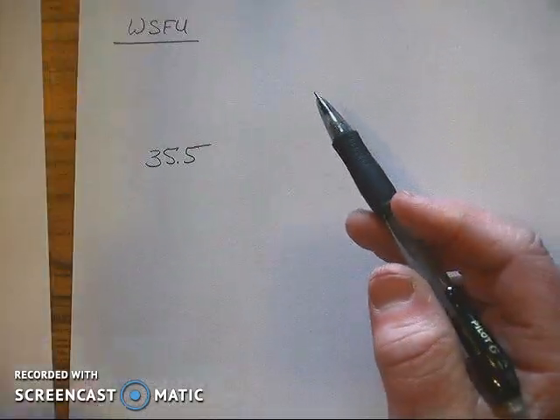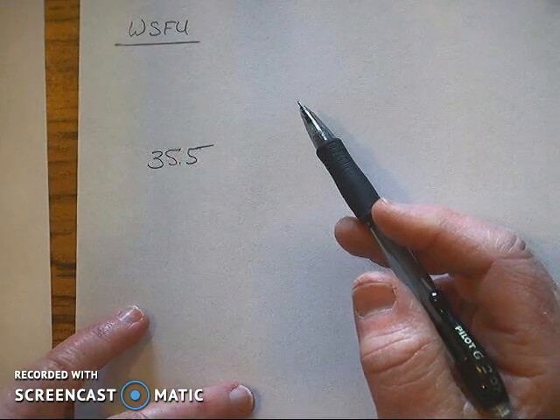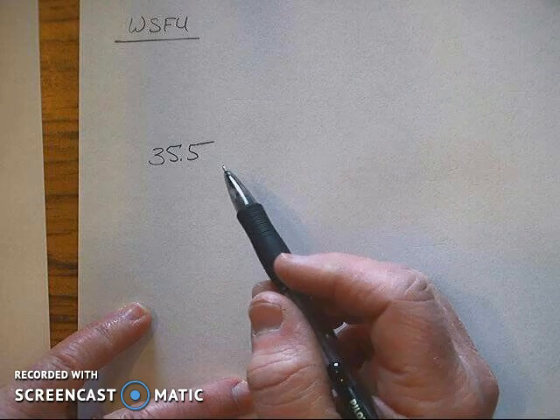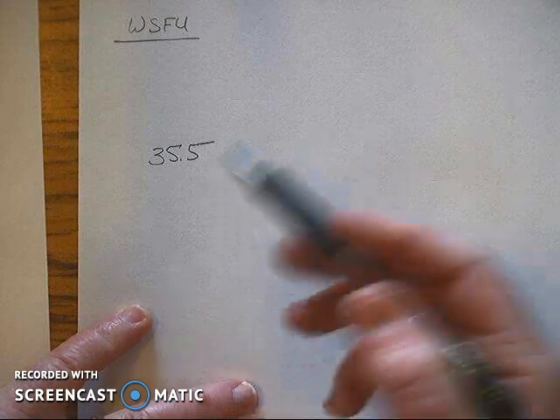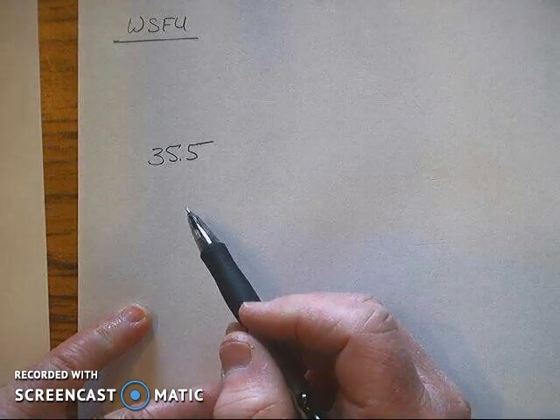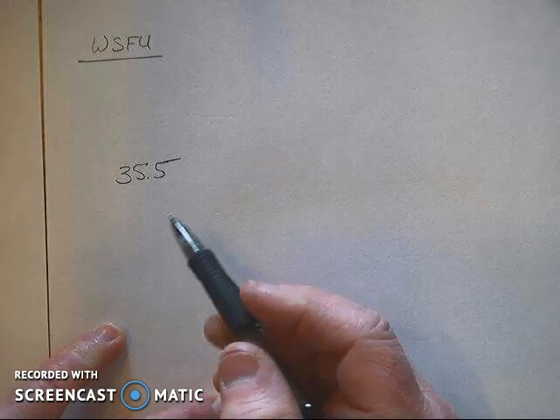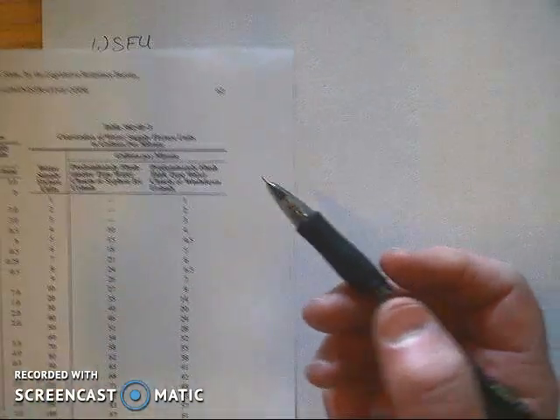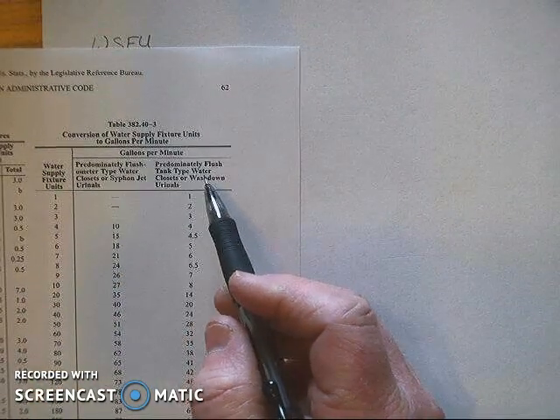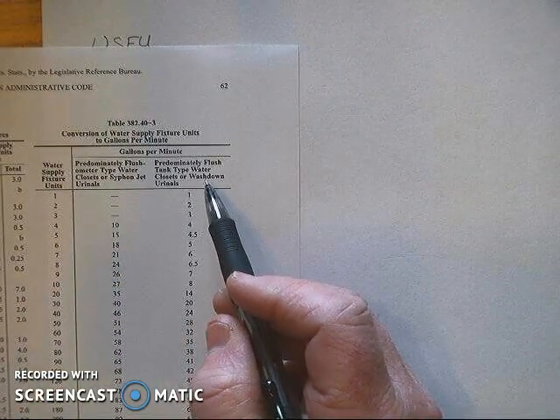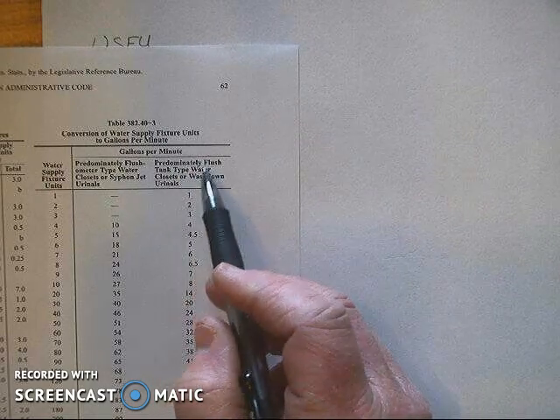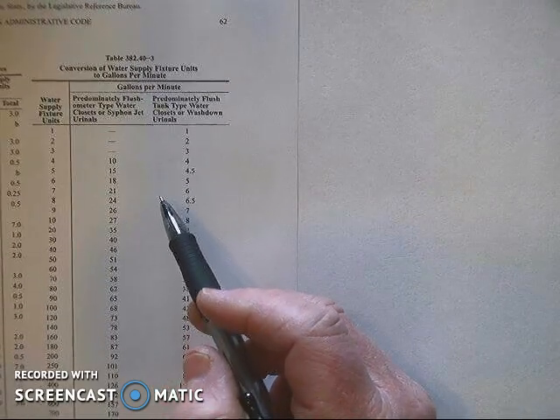To convert the water supply fixture units to gallons per minute, first we take the number of WSFU that we have. In this example I'm going to use 35.5 WSFU and we are going to convert it to predominantly flush tank fixtures for this activity. So the predominance will be for flush tank type fixtures. I will be using the right hand side of this table for this conversion.